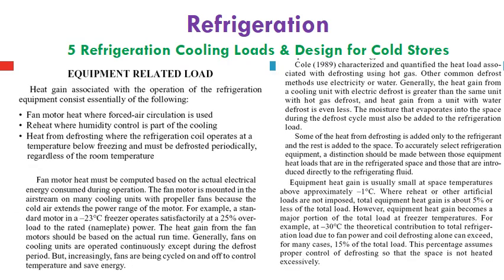Equipment related load is the fifth load component, which should be considered specifically according to the equipment with which the refrigerator is equipped. Heat gain associated with the operation of refrigeration equipment consists essentially of the following: fan motor heat where forced air circulation is used, reheat where humidity control is a part of the cooling, and heat from defrosting where the refrigeration coil operates at a temperature below freezing and must be defrosted periodically regardless of the room temperature.